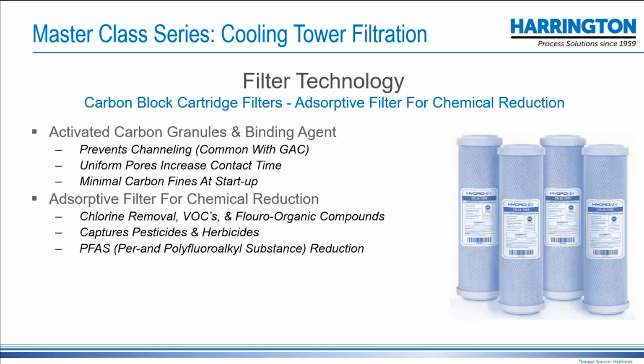If you've ever gotten a Brita filter, one of those countertop carbon filters, and you poured your first batch of water into it, you got all kinds of black silt. You have to rinse it several times before you can actually use it. Well, media systems are like that. But a carbon block is an impregnated resin. You don't ever get any release of the carbon fines into the final water. So for lower flows or for multi-round flows, it could be a good organics solution.